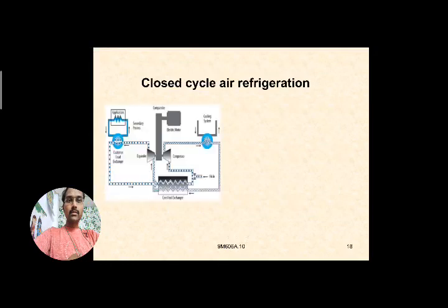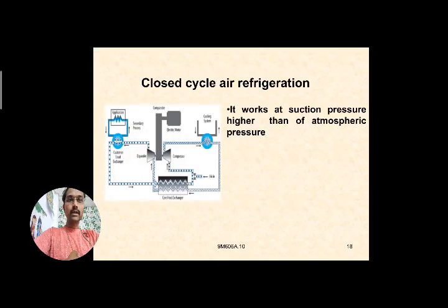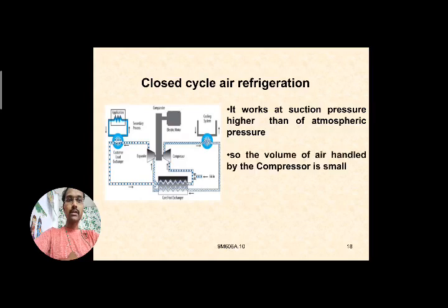Next, similarly, we will see a few points here. The suction pressure is higher than atmospheric pressure. If you observe the open cycle, it works at about the same as atmospheric pressure, whereas here in the closed cycle air refrigeration the suction pressure is higher than atmospheric pressure.